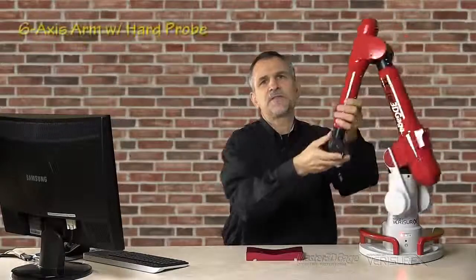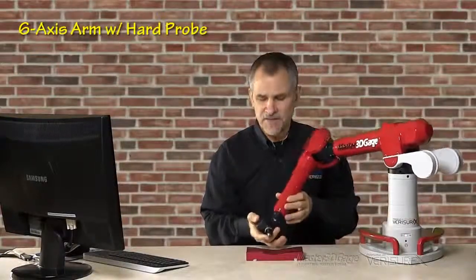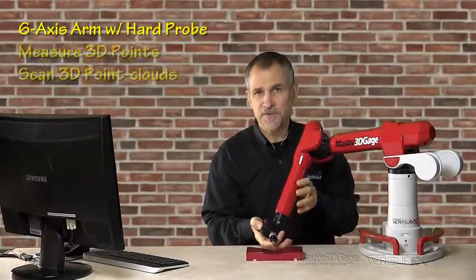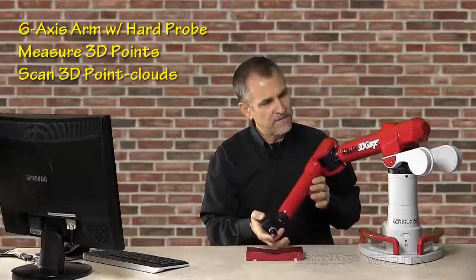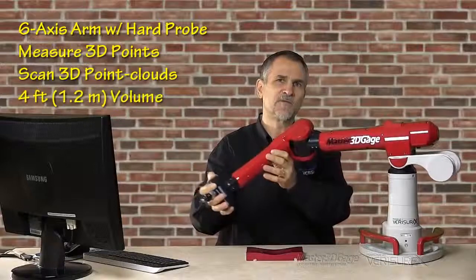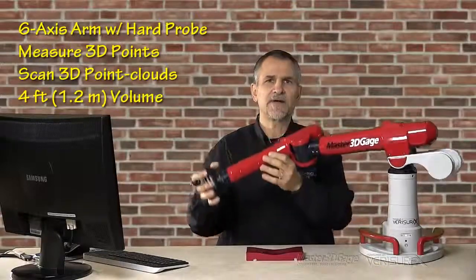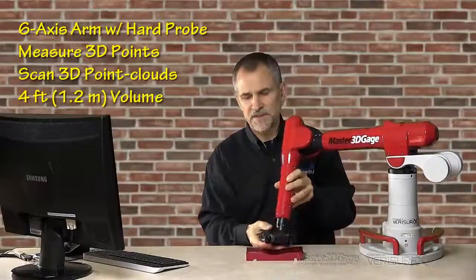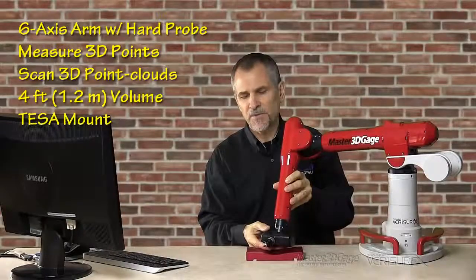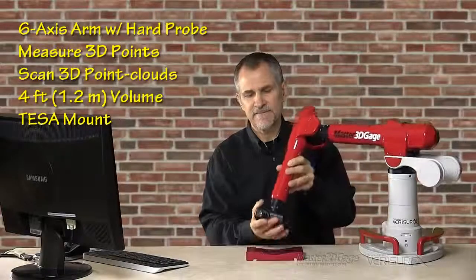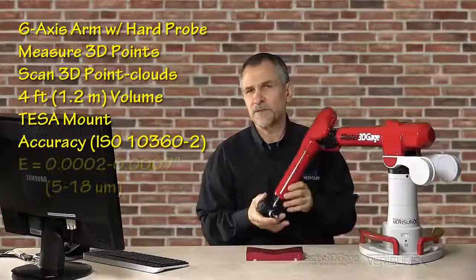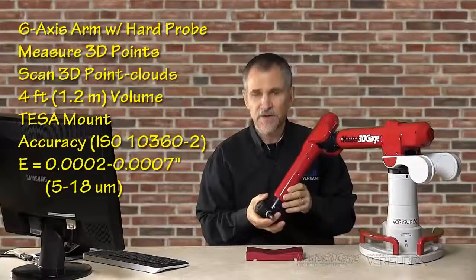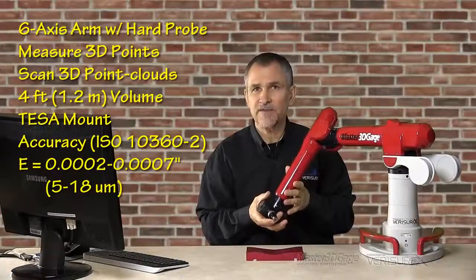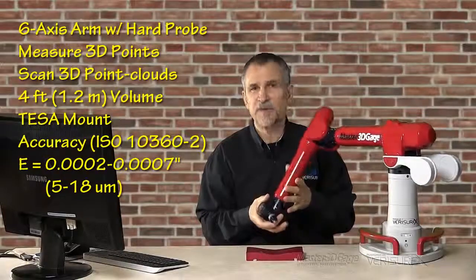The Master3DGage system comprises both hardware and software. The gauge itself is a 6-axis articulating arm CMM that uses a hard probe to measure 3D points and point clouds. The arm has a 4-foot volume, or a 2-foot reach in any direction. It uses a TESA mount that allows us to swap probes without having to requalify. Accuracy is between 2 and 7 ten-thousandths of an inch for characteristics such as position or length, depending on the size of the object we're measuring.